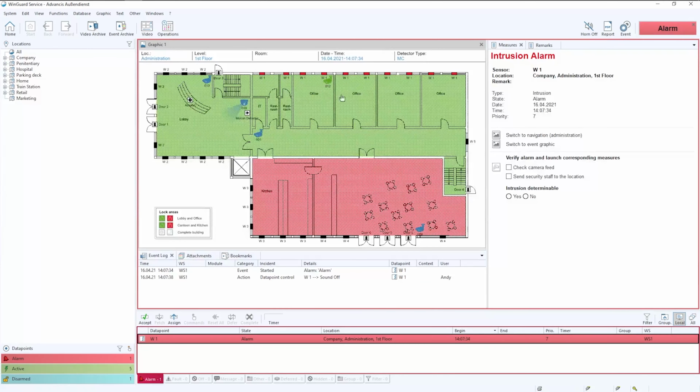You'll see that down at the bottom here, the intruder panel is showing it's a higher priority alarm, and it's shown with its location, the data point name, the endpoint name, along with the alarm type. If the operator selects accept, you'll see just above in the event log that it is accepted and assigned to a user. Across on the right, you'll see the dynamic workflows. This is where the standard operating procedures of the organisation are taken in and digitised in order for the operator to take the relevant actions.